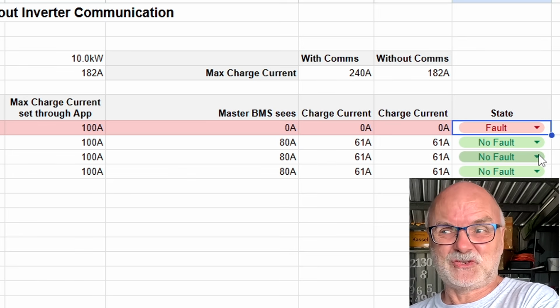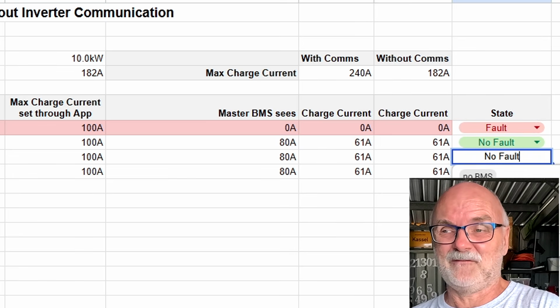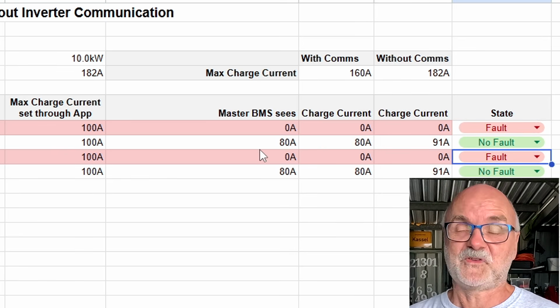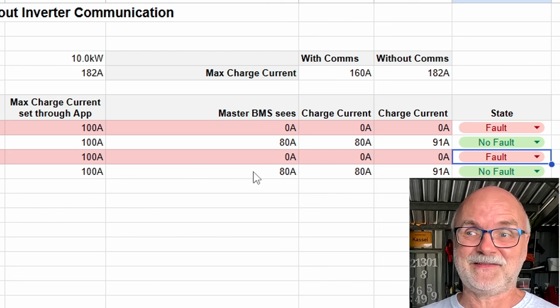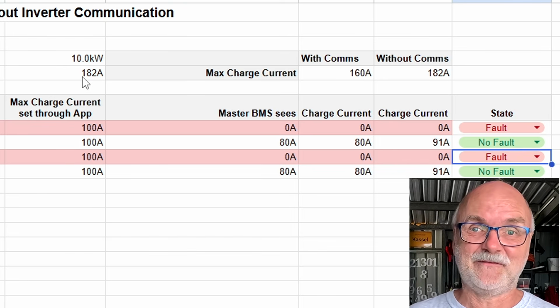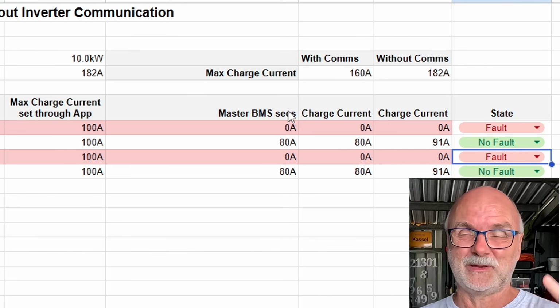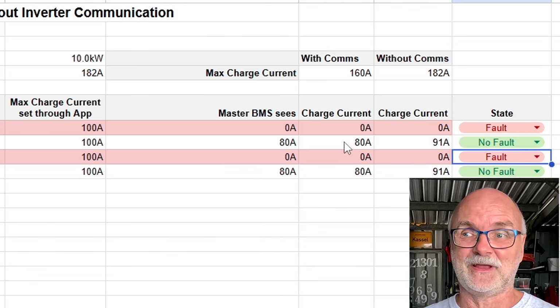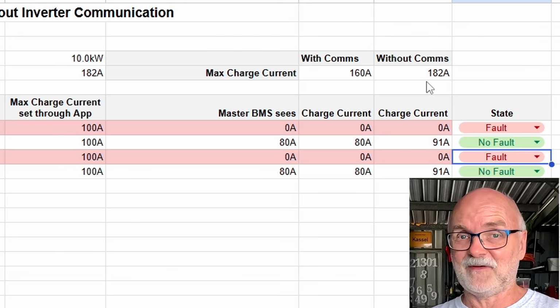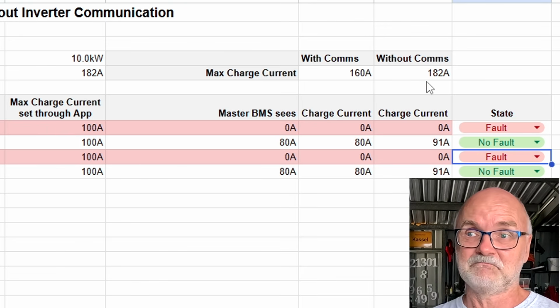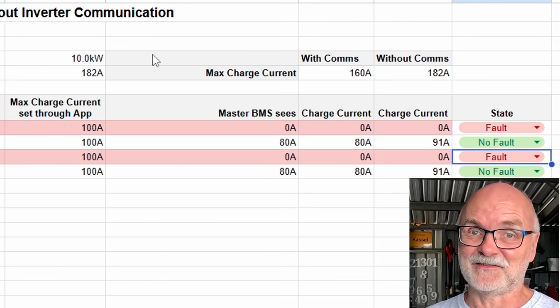Now you've got another temperature issue in one of the other BMSs. One of them trips out again. So here again, we've got 2 remaining BMSs, 80 amps each. We are requesting 160 amps from your inverter. The inverter can deliver 182 amps. So we get a bit of throttling here with the communication already, down to 80 amps. Very, very safe. We don't have any throttling without the communication because the charger doesn't know that 2 BMSs have failed.